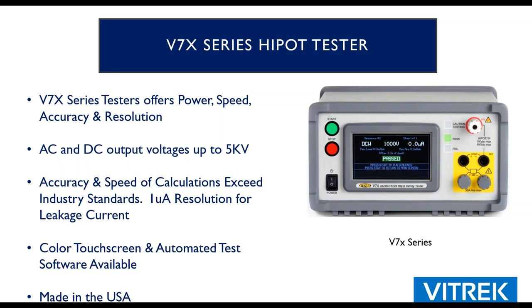So Vitrek basically has two mainframes of Hipot testers. The V7X series is shown here. It is a great production line tester. It's more compact than our other line of testers. It's a little less powerful, but still sufficiently accurate. Depending on the version that you're looking at, it can offer AC/DC Hipot, insulation resistance, ground bond, and continuity. Pretty much everything that we talked about before, minus the ground leakage test.